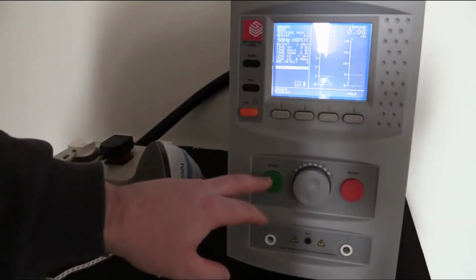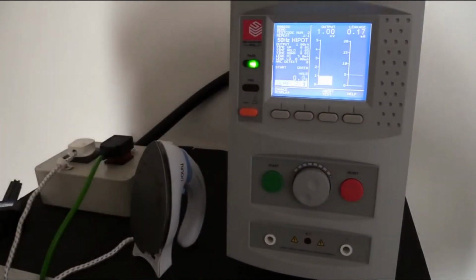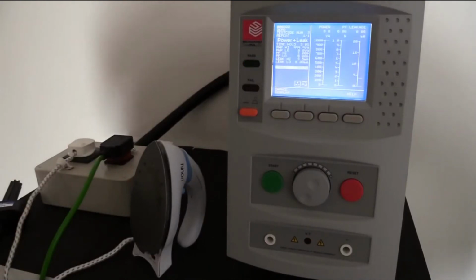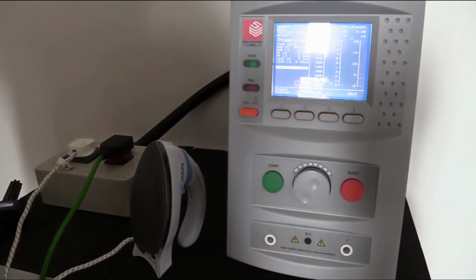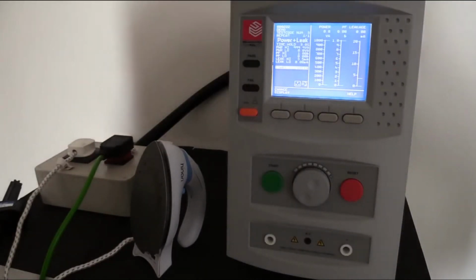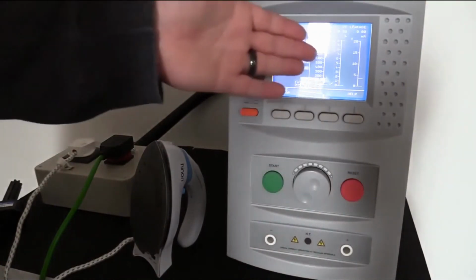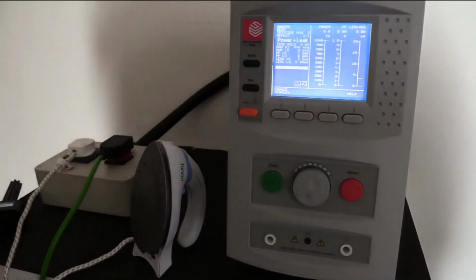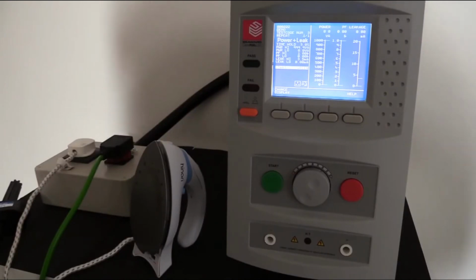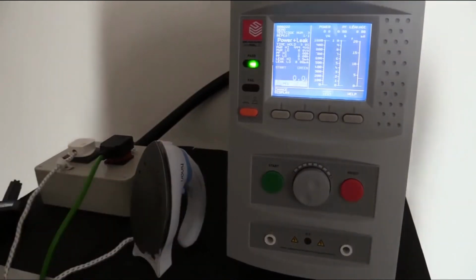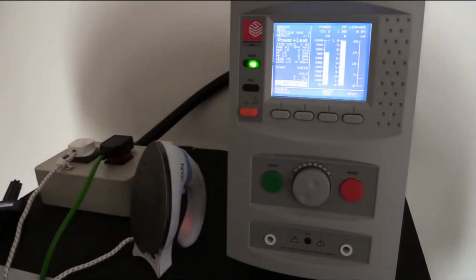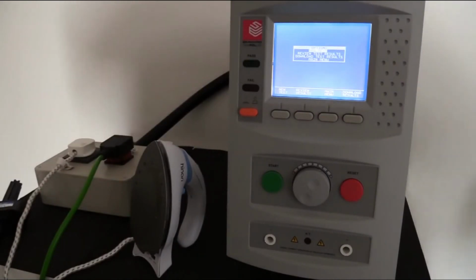We'll start the test away. The unit will output 1000 volts for a second. Providing the leakage again is less than the limit, the test will pass and move on to the next test. And the final test here now is a run test. So we're going to power the iron up. We will get an indication of the amount of power the thing pulls, in this case via a VA reading, and it will also give us any earth leakage flowing back into the device under normal operating conditions. So again, we'll just press the green button. The test is started. We can see it's pulling around 730 VA. Test is complete. The sequence is over.